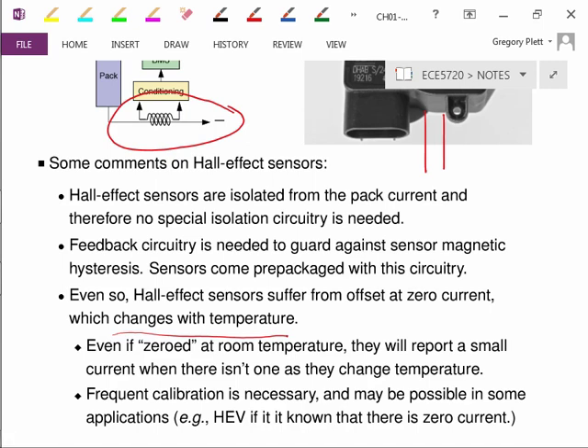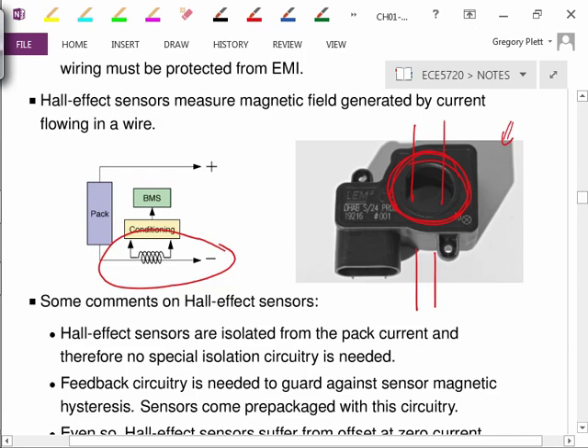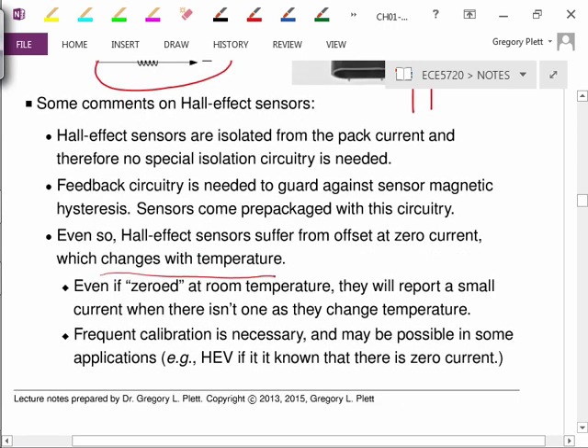I've worked with these before, where we zeroed the offset at room temperature—fully calibrated—then put the thing into a temperature chamber and changed the temperature, and the reported current changed by between 1 and 2 amperes. That doesn't seem like a lot if the peak current of this device is 600 or maybe 500 amperes. But we were using it with a 5 amp hour battery pack, and if I simply integrated a 1 amp erroneous offset for 1 hour, that would make my state of charge estimate off by 20%.